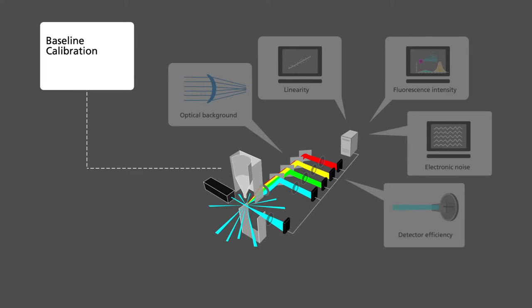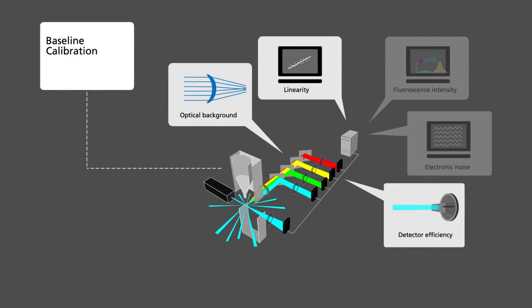At each calibration, data is compared to the baseline and is typically done weekly. This calibration comprises, among others, of measuring factors like linearity, detector efficiency, optical background, and electronic noise. We also determine the fluorescent intensity for each parameter that maximizes its resolution.